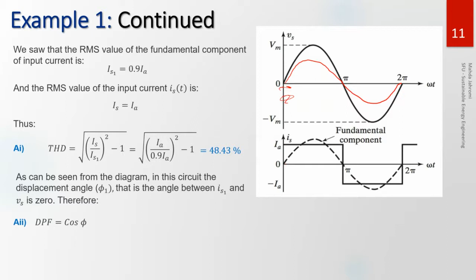So the phase angle is 0. If the phase angle is 0, the displacement power factor, which is cosine of phi, is 1. So the displacement power factor is 1, but the actual power factor, which also has the harmonic component in it, is not 1. It's actually 0.9. So what we've been calculating as power factor until now was actually displacement power factor.